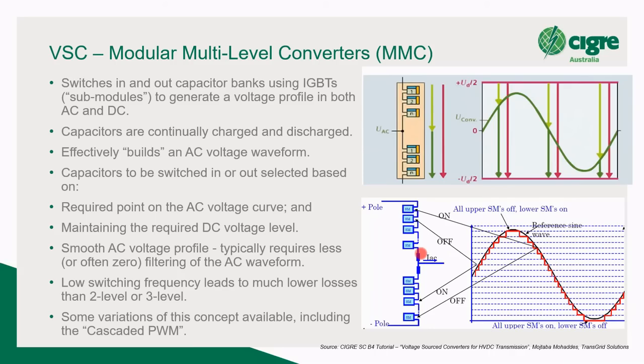For the MMC, same thing applies. It's just you put in more modules so that if any of these fail, they bypass. And there are different technologies, different ways in which the bypass is done. They will bypass, they'll take themselves out of the circuit. And because you've got enough capacitors to cover that number, then the converter will continue to operate. Of course, there'll be a protection in there that will say, when you get close to your number, it'll give you an alarm. When you exceed that number, it'll trip the converter.